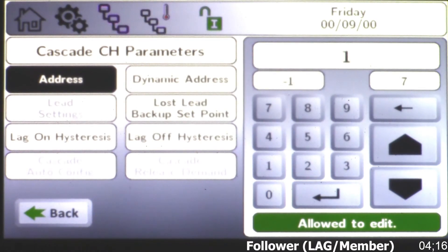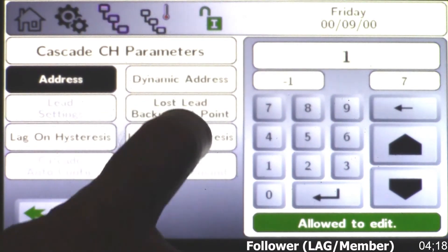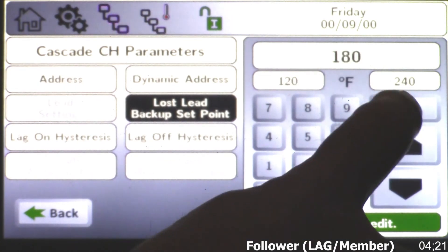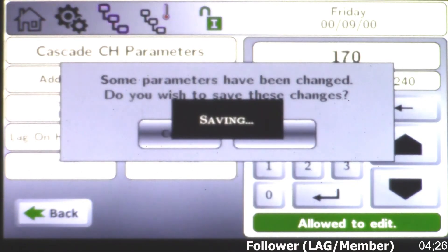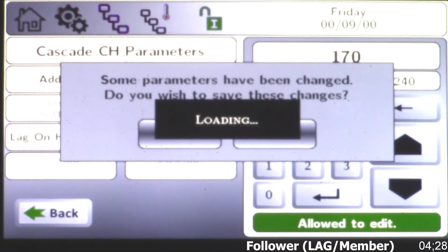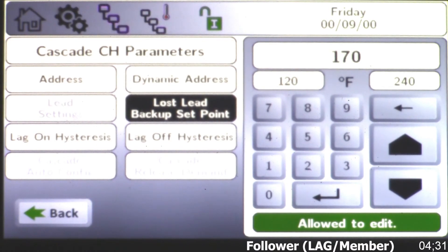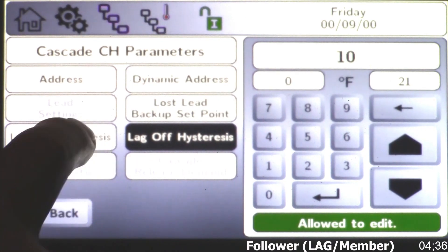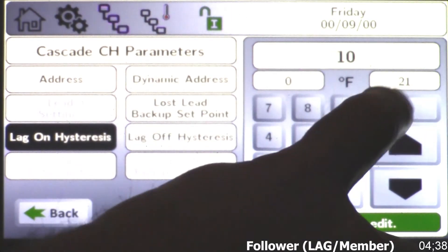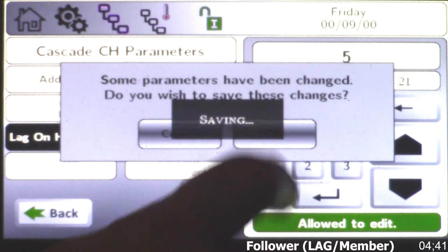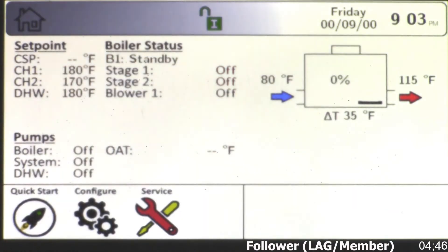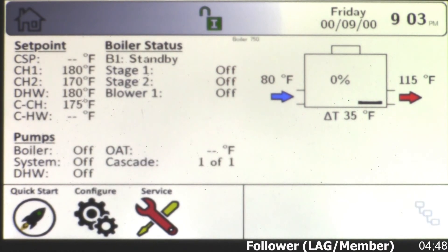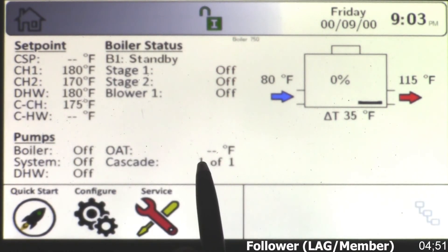While I'm here, I want to get into lost lead backup setpoint. On our lead boiler we chose 170, so we're going to keep this at 170 — that will carry through. You want to do that on each member boiler. We're only cascading two here. You can also set your off or on differentials — I think we chose five degrees previously. Now when I go back to my home screen, you'll see cascading appear — be patient.